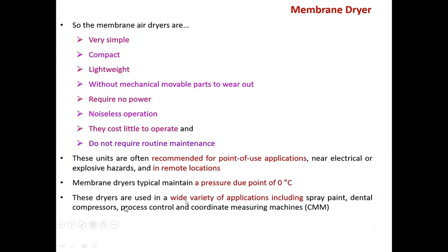The membrane dryer typically maintains a pressure dew point of 0 degrees Celsius. These dryers are used in a wide variety of applications, including spray paint, dental compressors, process control, and coordinate measuring machines.